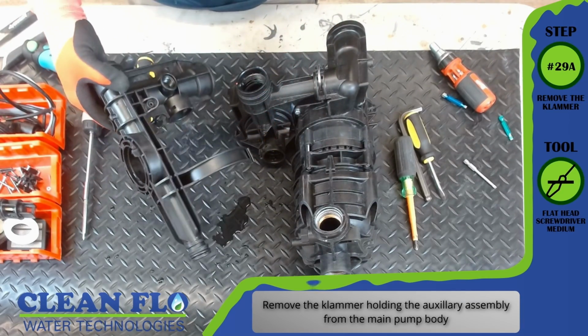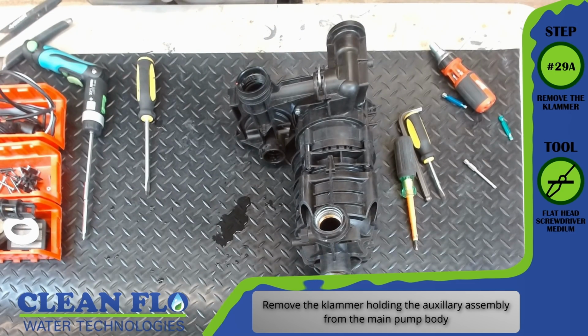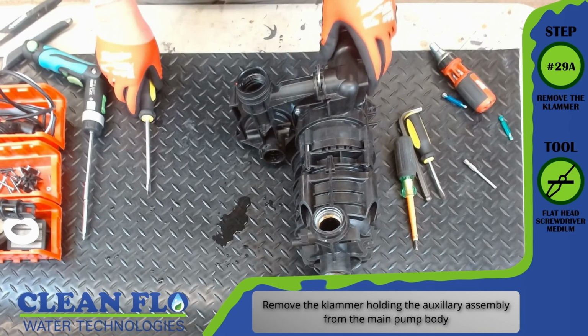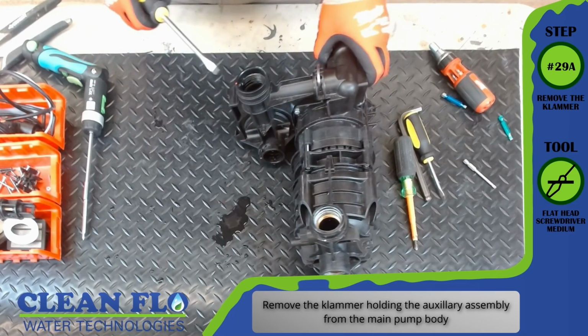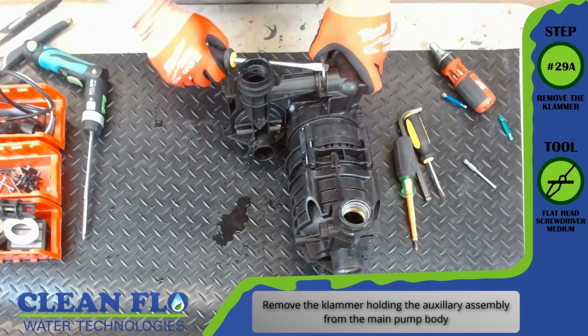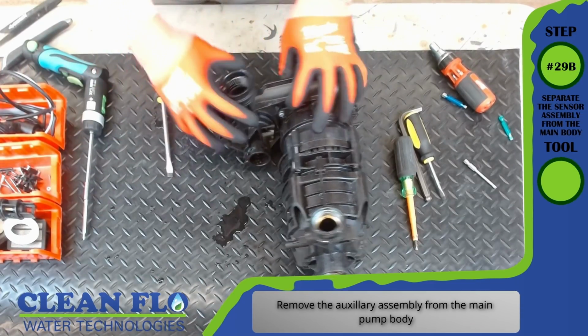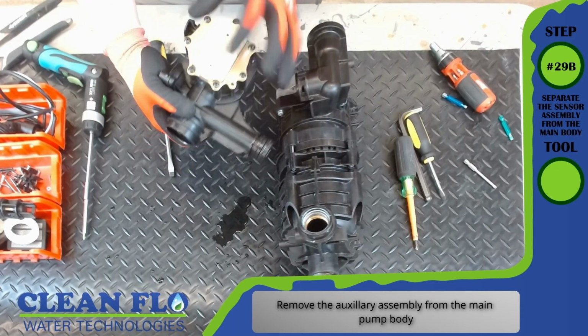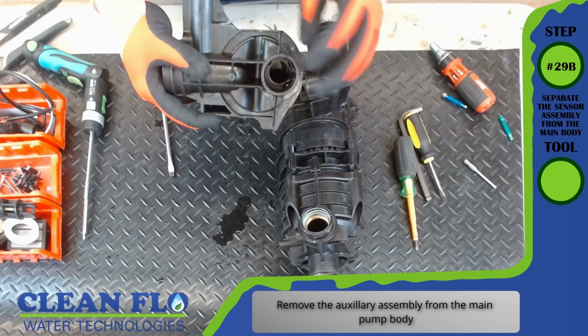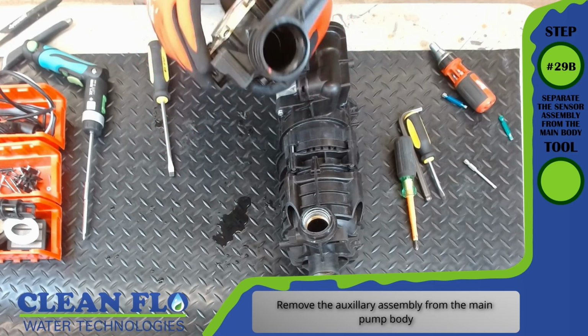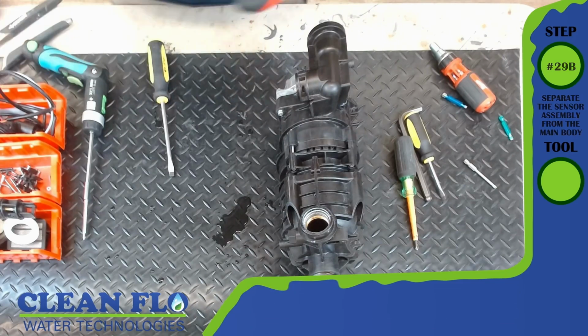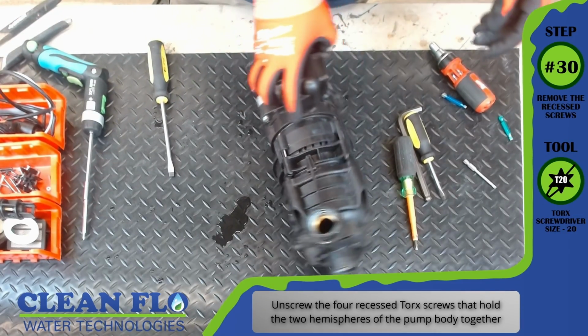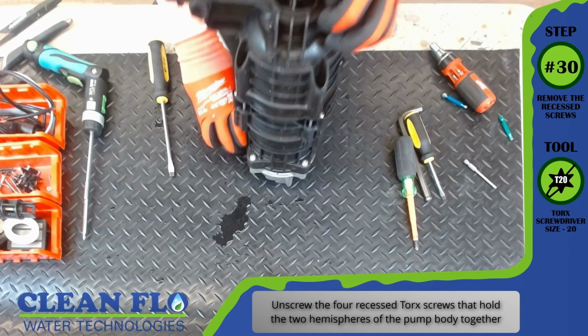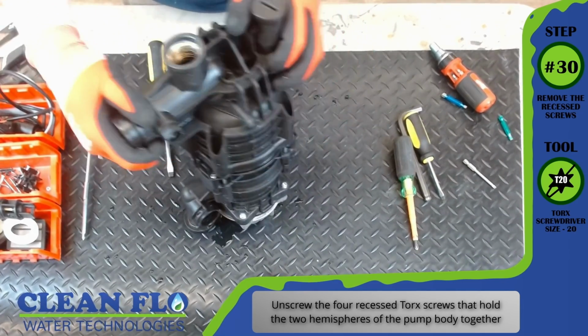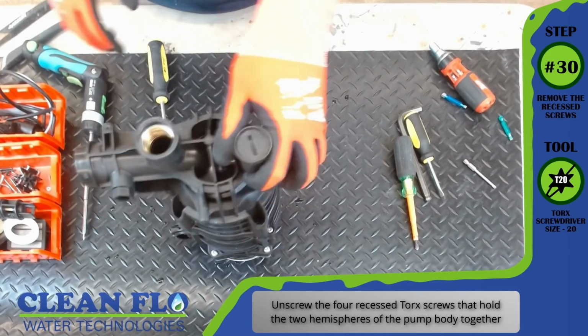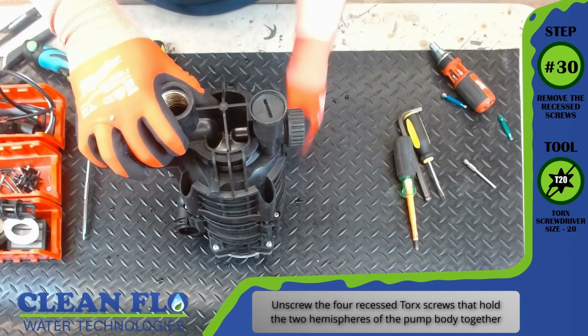Step number 29A, remove the clamp. Tool, flathead screwdriver, medium. Remove the clamp holding the auxiliary assembly from the main body. Step number 29B, separate the sensor assembly from the main body. No tool is required. Remove the auxiliary assembly from the main pump body. Step number 30, remove the recessed screws. Tool, T20 Torx screwdriver. Unscrew the 4 recessed screws that hold together the 2 hemispheres of the pump body together.